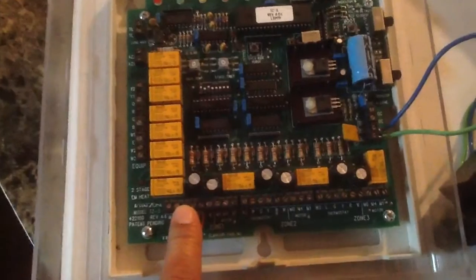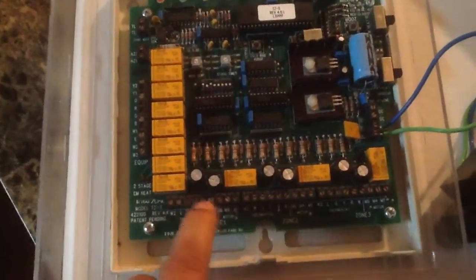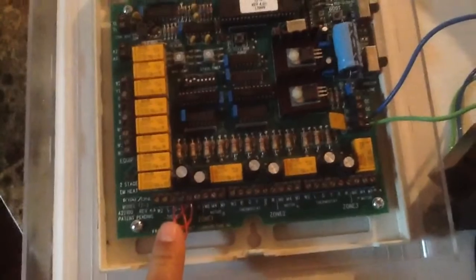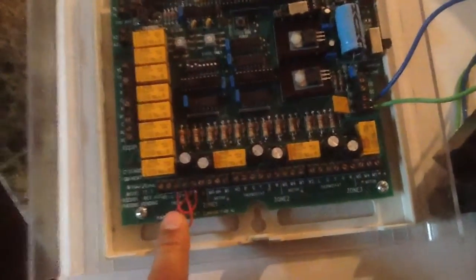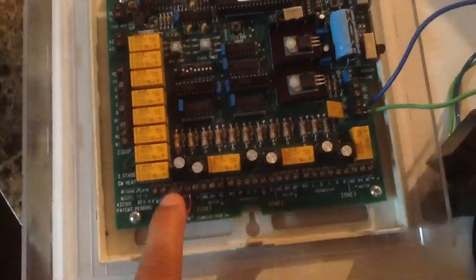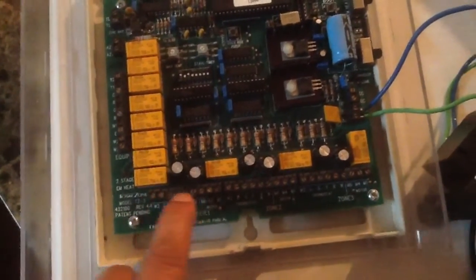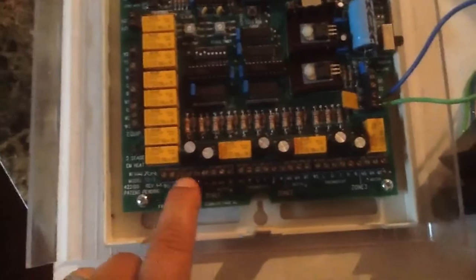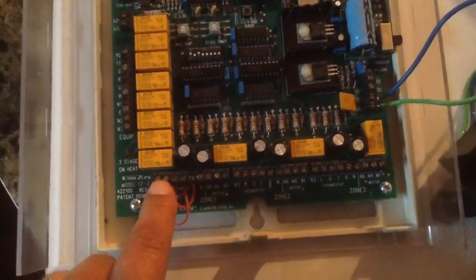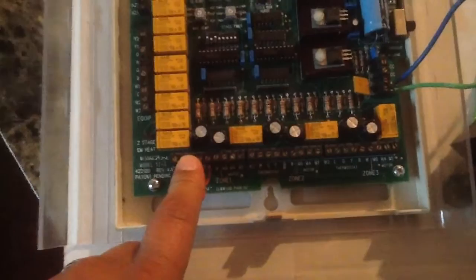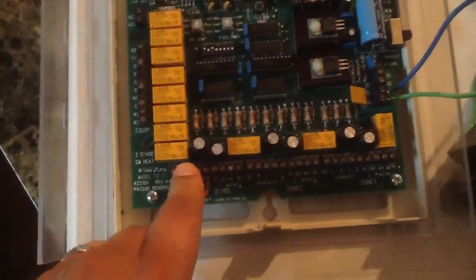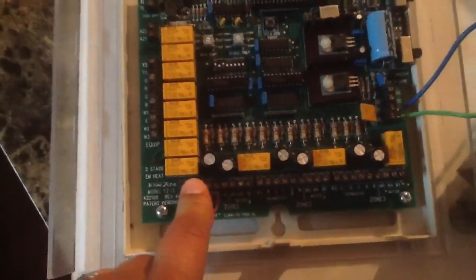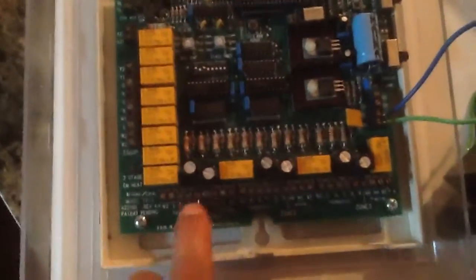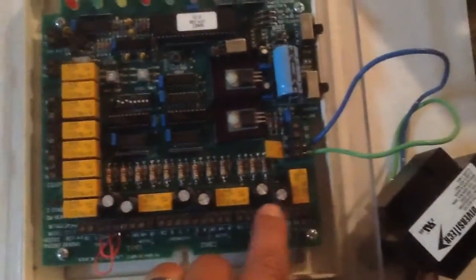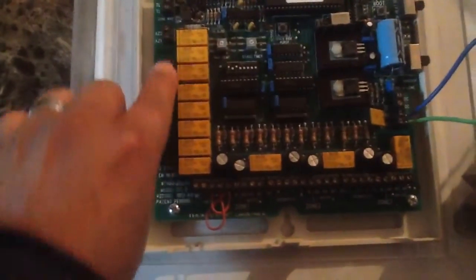It's just all about inputs and outputs. If you look at your zones, if your thermostat's calling, you can verify that here. So if I know the thermostat's calling for heat on zone 1, I go to common and W here, and if I get 24 volts between common and W, I know my thermostat's calling. That eliminates the low voltage wiring from the thermostat to the board, and the thermostat. And if I have my input, I should be getting my output, which is over here. Here's all your inputs, zone 1, zone 2, zone 3, and here's all your outputs.